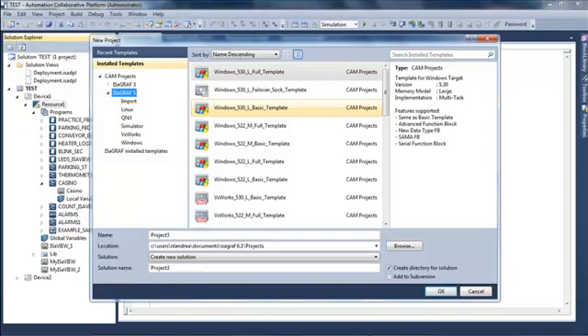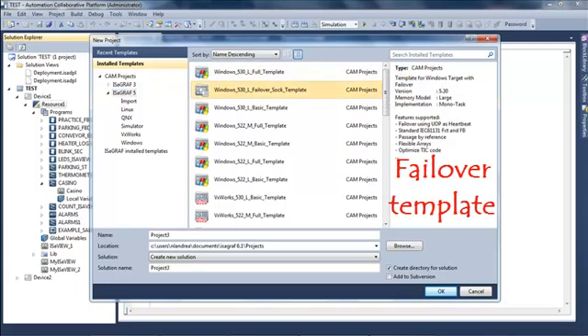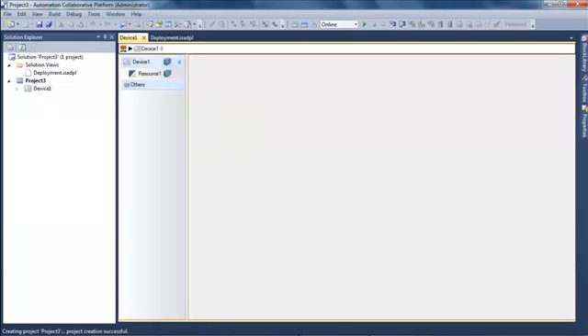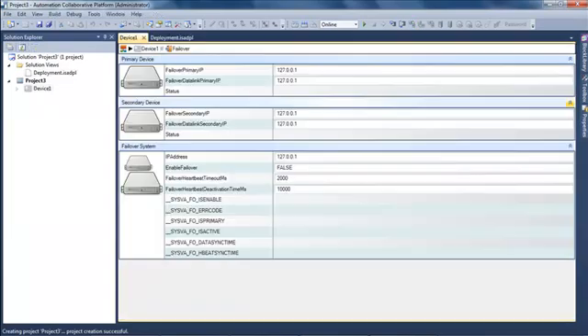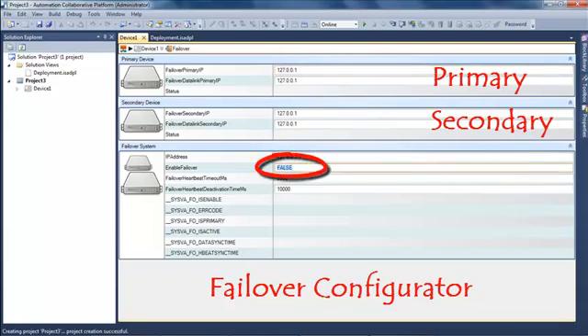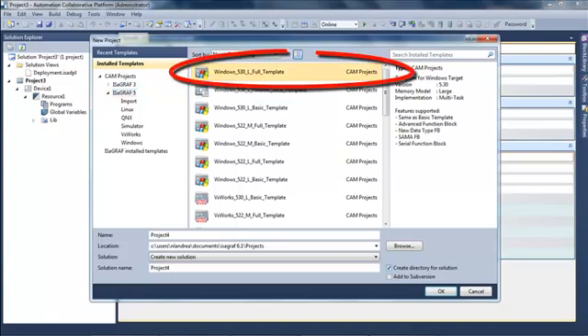I'm going to create a new project based on a failover template to show how to configure a failover system. You can see that the device icon is different because it shows two PLCs. In the device view I can select the failover plugin, where I can configure the IP addresses of the primary and secondary systems, configure timeouts, and view system variables concerning the failover.